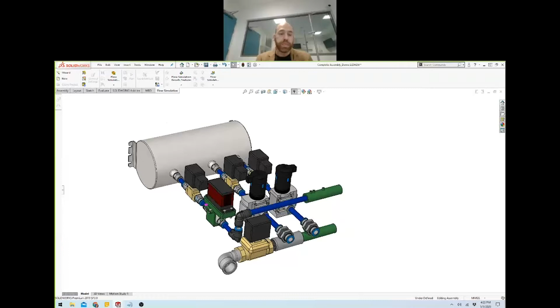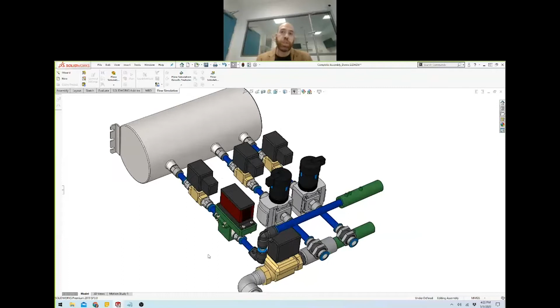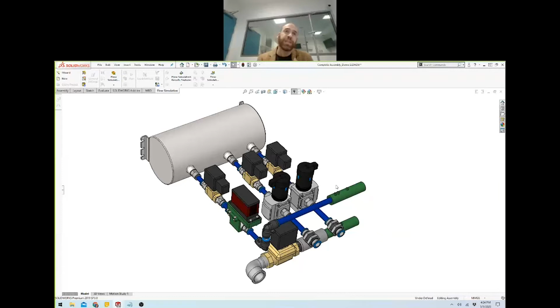This particular design is good for transportation, for short term, but you cannot put a patient on long term with an ambubag centered design. First of all, it has limitations regarding the volume it can give. It has limitations regarding the waveform, how we're putting in the air inside the patient. Is it too fast? Is it too slow? Is the pressure rising too fast? It is very slow as a system, so it cannot react to a patient that is actually trying to cough or needs a bit more air at the same time. So this is where the problem with the ambubag is, and plus the fact that the ambubag, by definition, was not designed to run hours and hours and hours and days upon days.